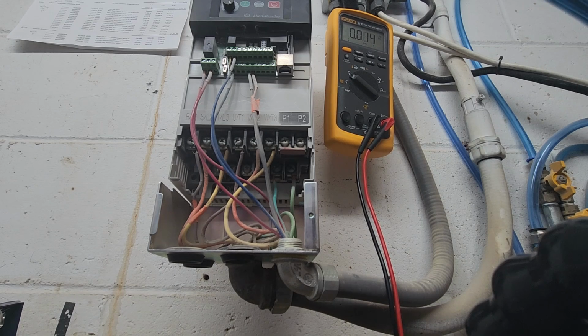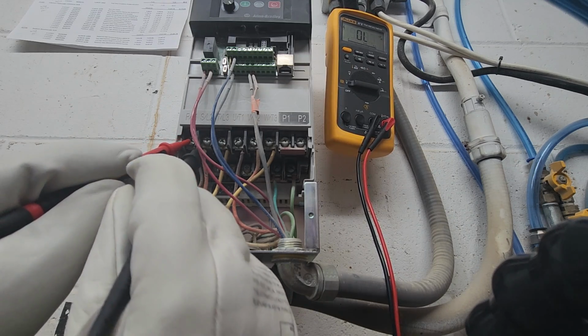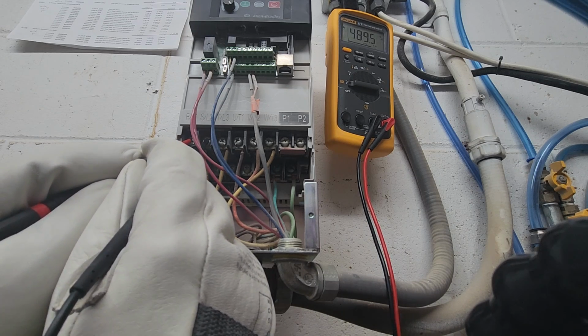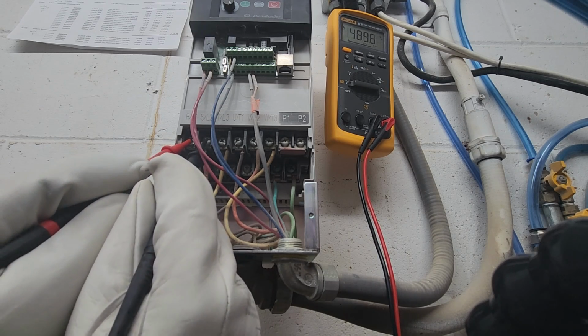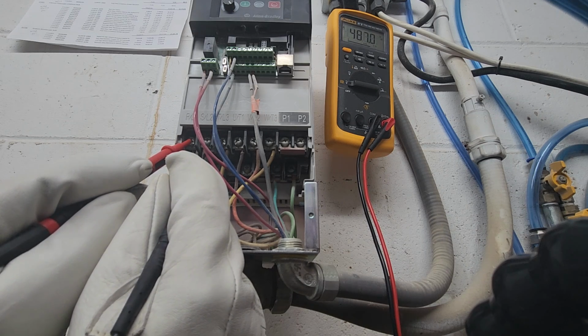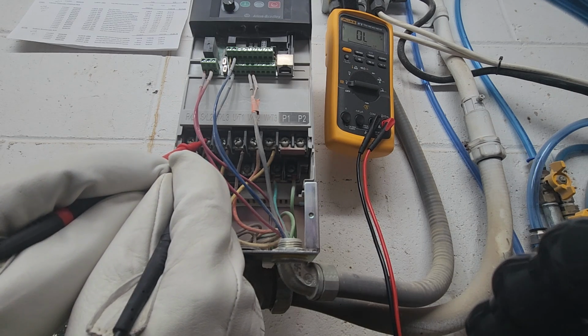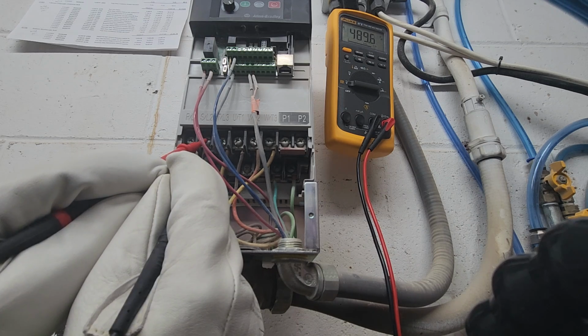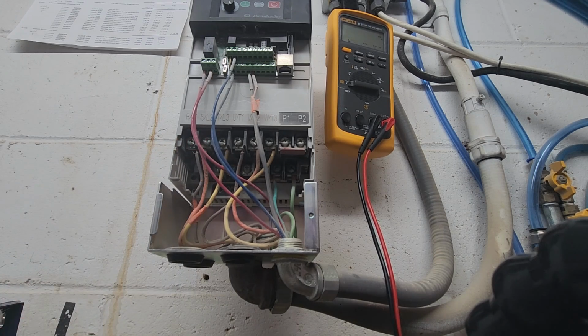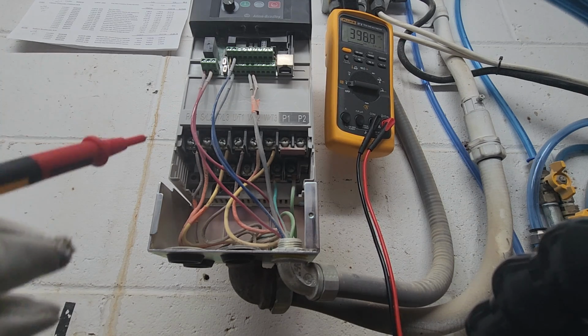being able to hang my voltmeter somewhere where you guys can see it, and also where I can get to these contacts. But okay, so we've got our voltmeter in volts AC. We're going to check our line coming in just to verify that the VFD is getting proper power. So we should have 480 volts between phases. This is L1 and L2, 480, L1 and L3, 480, L2 and L3, 480. That's perfect. So we've got good power coming into the VFD.